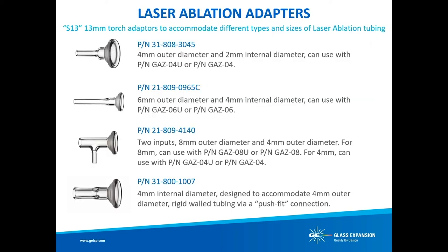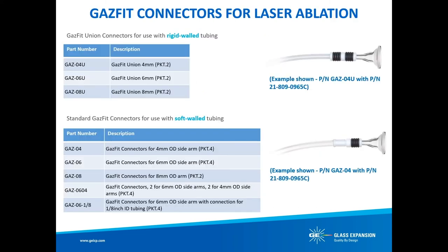Laser ablation was covered in great detail in our most recent webinar. Glass Expansion has designed several different laser ablation adapters to improve reliability and ease of connection from the laser ablation system to the ICP-MS torch. Various styles accommodate an S13 or 13mm torch connection along with different types and sizes of laser ablation tubing. Glass Expansion's GazFit connectors also provide a convenient and reliable connection of laser ablation tubing to one of our adapters for a direct connection to the ICP torch — all GazFit connectors are manufactured from PTFE with a seal made via external O-ring pressure.